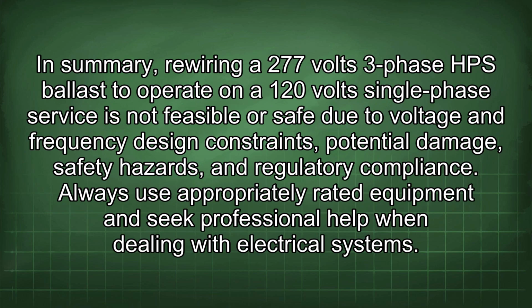In summary, rewiring a 277 volts 3-phase HPS ballast to operate on a 120 volt single-phase service is not feasible or safe due to voltage and frequency design constraints, potential damage, safety hazards, and regulatory compliance. Always use appropriately rated equipment and seek professional help when dealing with electrical systems.